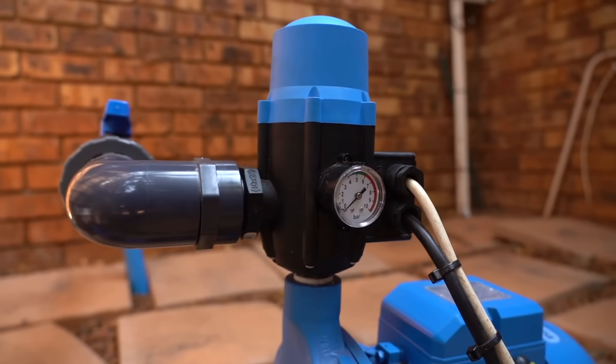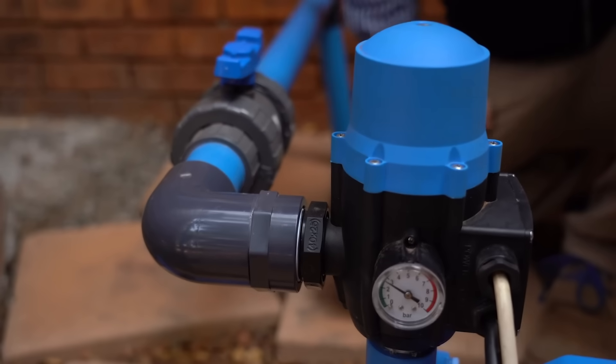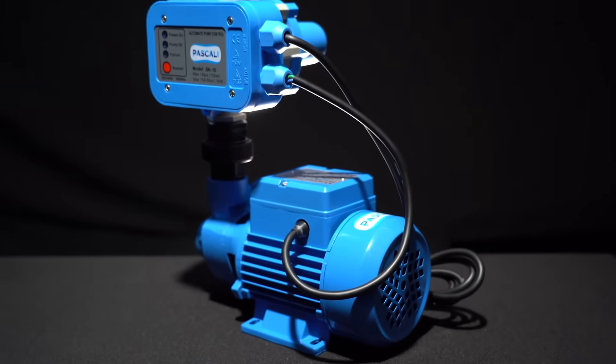Between the lines, in this case size does matter. As we've mentioned, flow and pressure work hand in hand — when one goes up the other drops. The more taps that are open, the less pressure you're going to have, and you have to be able to supply that. For a single person, a small 0.37 kilowatt pump will be sufficient; for a family of eight, we're moving more towards a 2.2 kilowatt range.